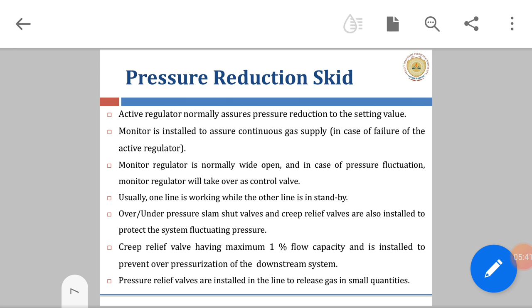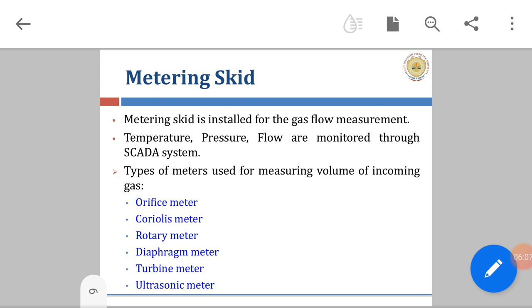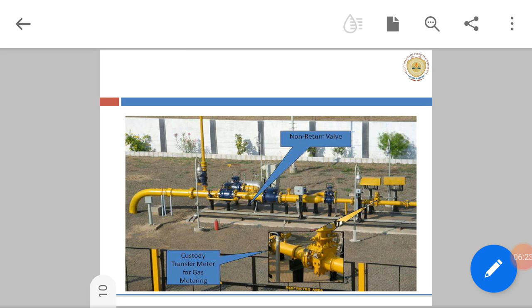We also need to meter the gas. Metering skid is installed for the gas flow measurement. Temperature, pressure, flow are monitored through SCADA system. Types of meters used for measuring volume of incoming gas are orifice meter, Coriolis meter, rotary meter, diaphragm meter, turbine meter, and ultrasonic meter. Now here is also a diagram which shows the non-return valve and also the custody transfer meter system for gas metering.